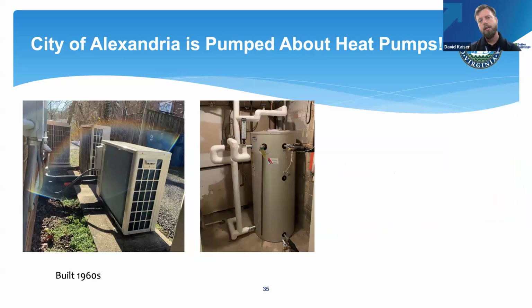This is a fun one. Again, another building built in the 1960s. It's an apartment building, and the way we changed it out was into an air to hot water heat pump. This is 100% heat pump. There's no electric resistance backup. This is a standard exterior condenser on the outside of the facility, and it feeds an interior storage tank and circulates water throughout the building for all the domestic hot water needs of the facility. It's about 12 units in this facility, so the occupants can get all their hot water needs met.